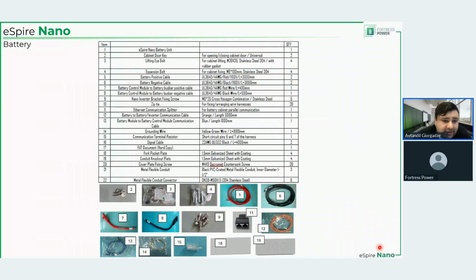Number 18 and number 19, these are the plates that I was talking about. 18 is for fork pockets, so it's just a flat plate with two holes for screws to secure it onto the base. Number 19 also has 2 screws for the holes, but also 3 knockouts for you to be able to connect the battery to inverter conduits to it. And the other things that are not shown on the photos, they are here. The battery guide will have this exact same thing. And as I said, you will get the PDF so you can look over it one more time.